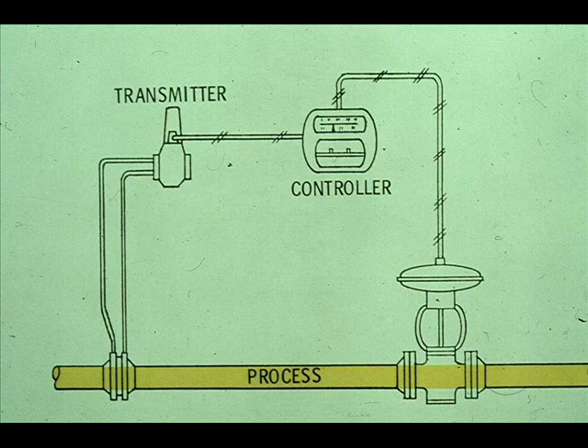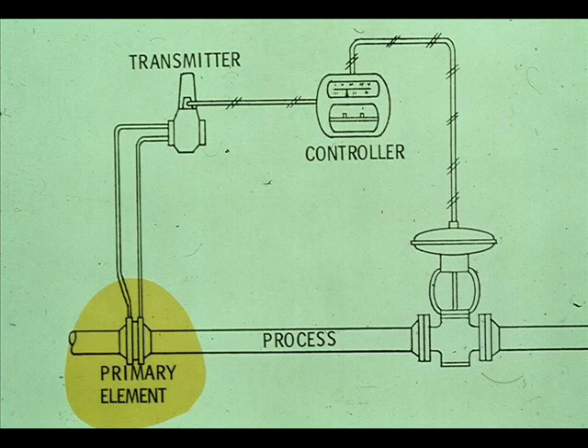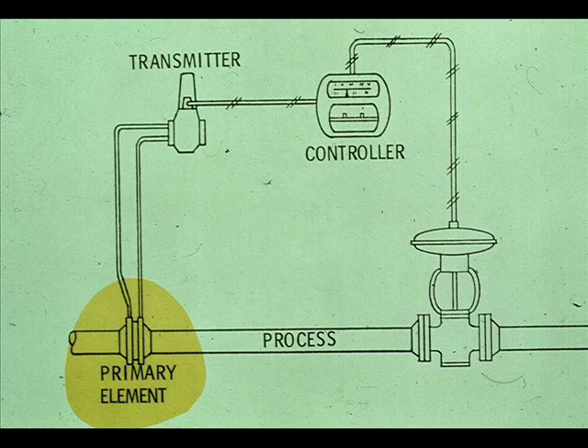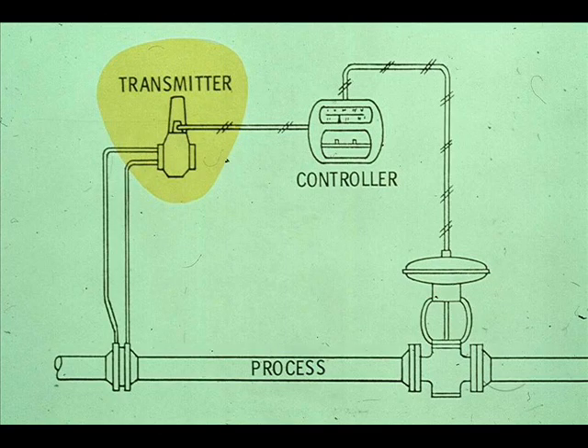Let's look again at a flow control loop. The process or system being controlled is the flowing stream. The process variable is flow rate. The orifice plate is the primary element. It measures delta P, which can be used to calculate flow rate, the process variable. The transmitter, frequently a differential pressure cell, converts the measured delta P into a signal which is proportional to the delta P, and transmits it to the controller.